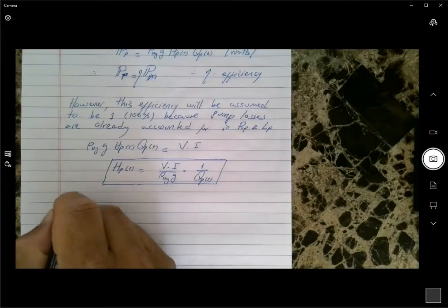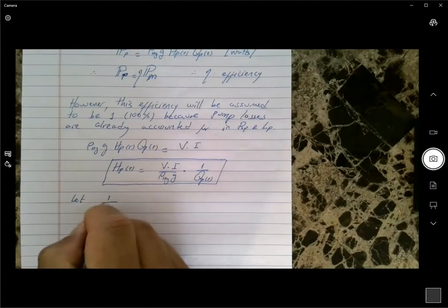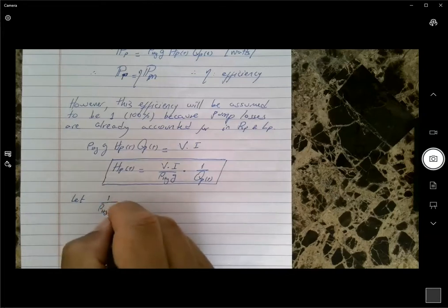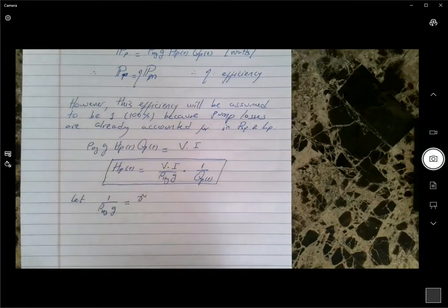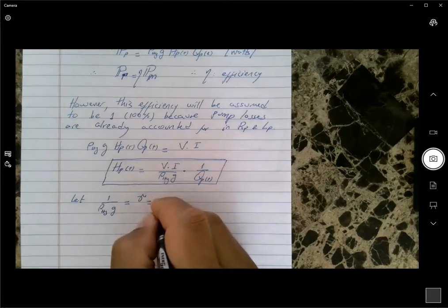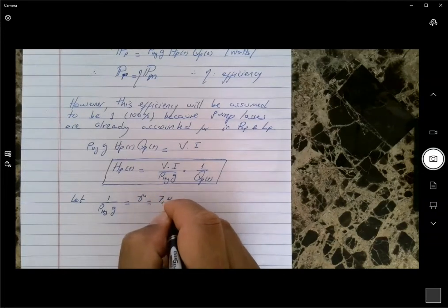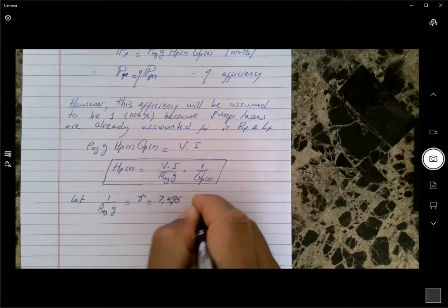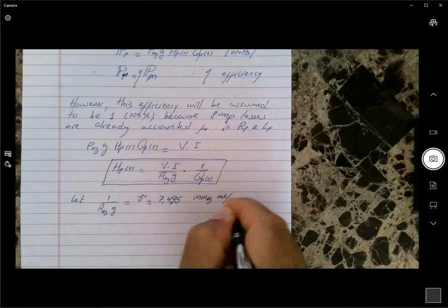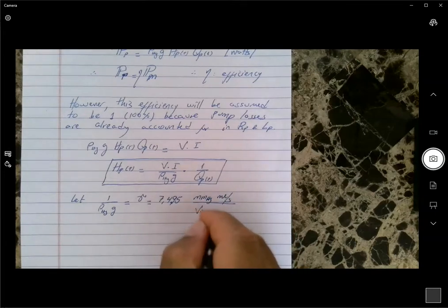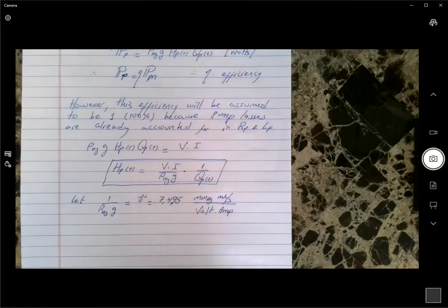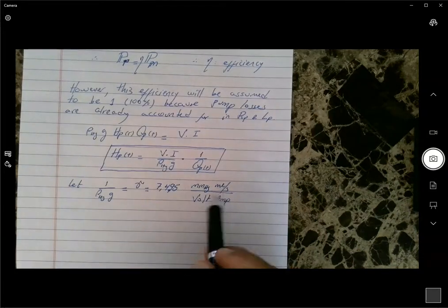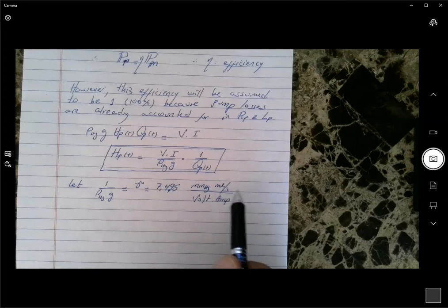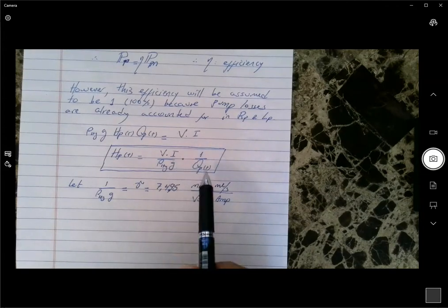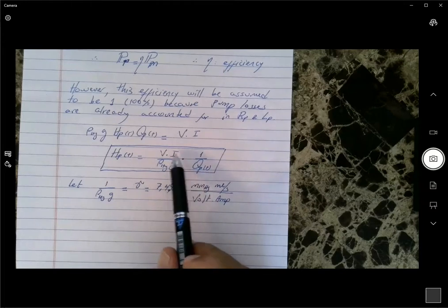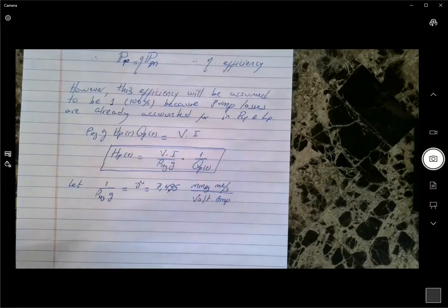So if we let 1 over rho_hg times gravity be equal to some parameter gamma, so we don't have to always enter those values and do the unit conversion, this turns out to be 7,495 millimeters of mercury times milliliters per second divided by volt-amp, which is watts. Volt times amps is watts. So this is already formulated in the appropriate units of millimeters and milliliters per second, so that you can enter the flow in milliliters per second and the voltage and current in volts and amps.